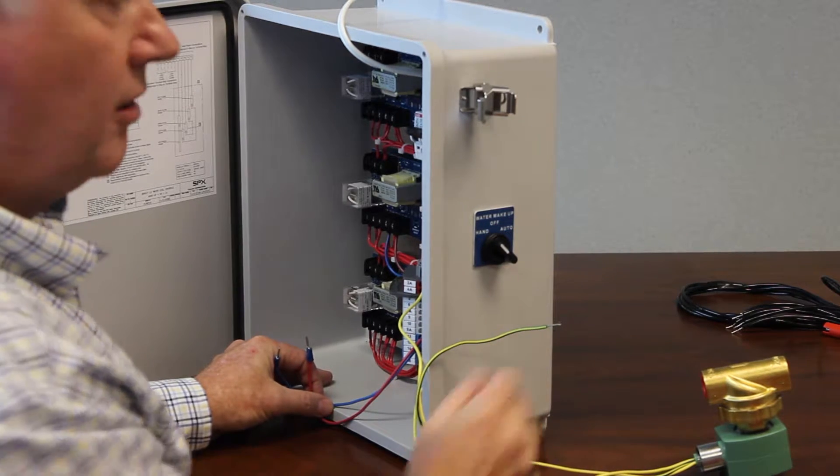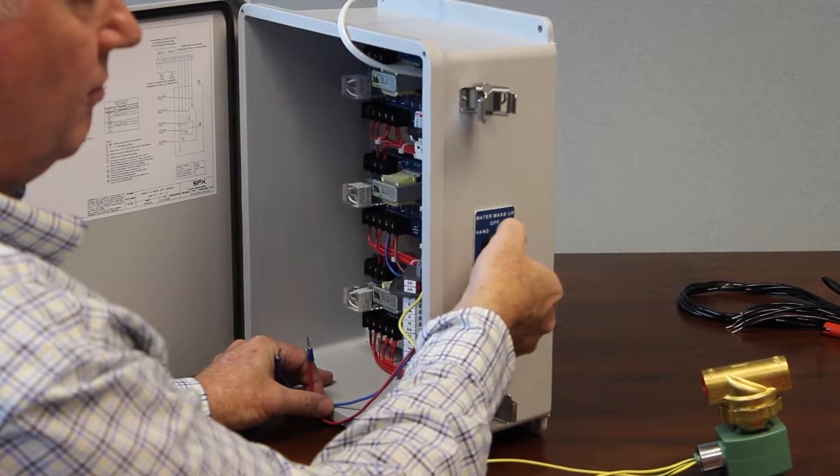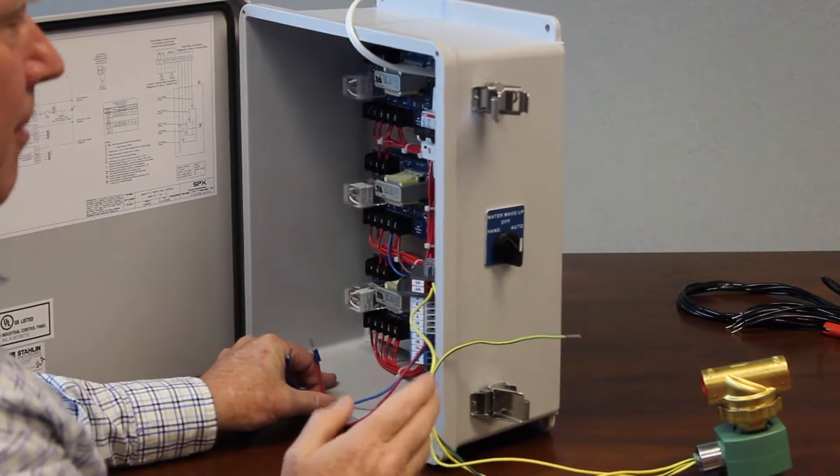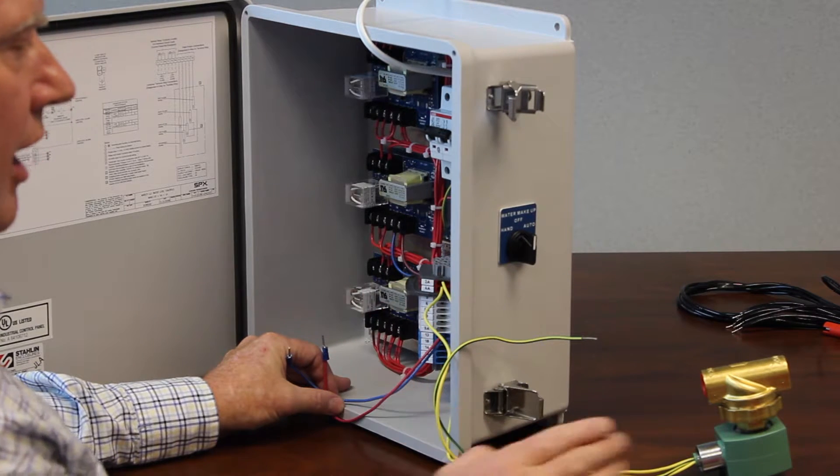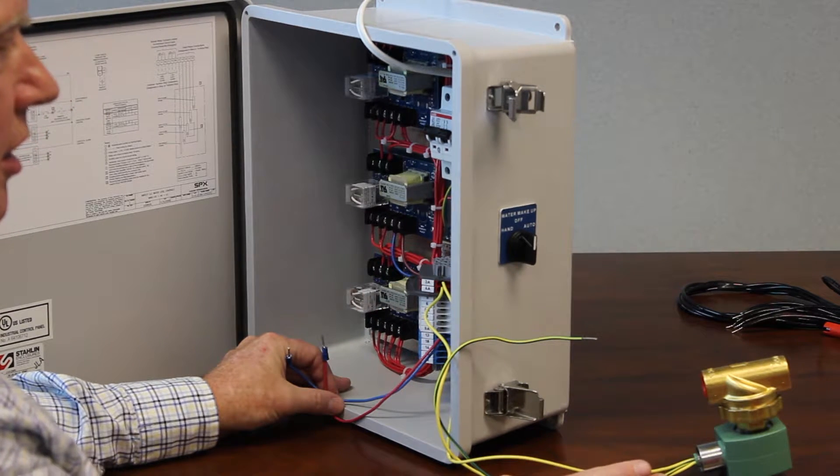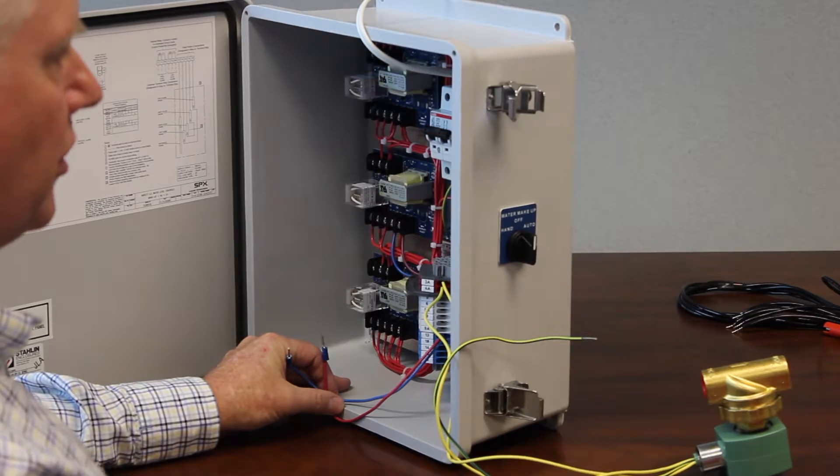Okay, I'm definitely on, off, on and off. So what that proves to me, that proves to me that the power flow from our panel out to the solenoid is good, and the solenoid seems to be functioning properly.